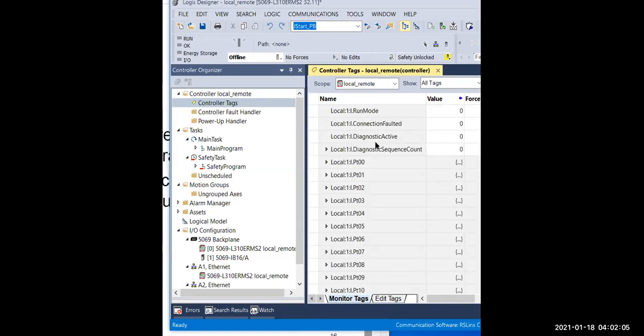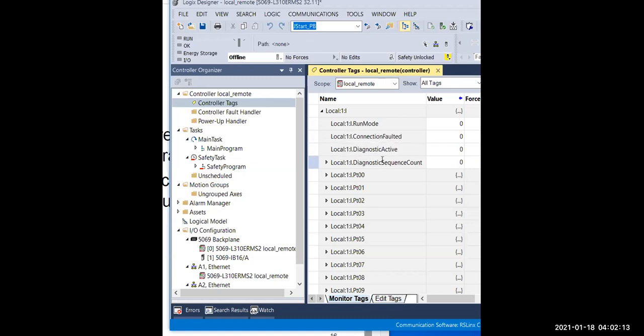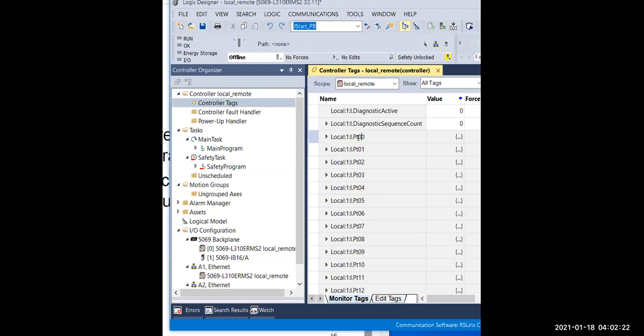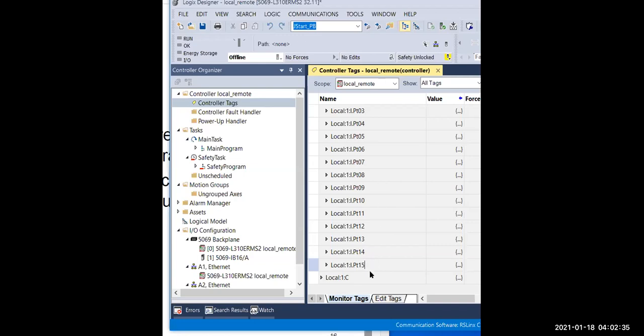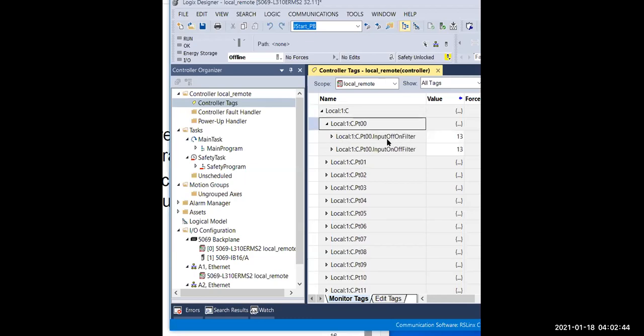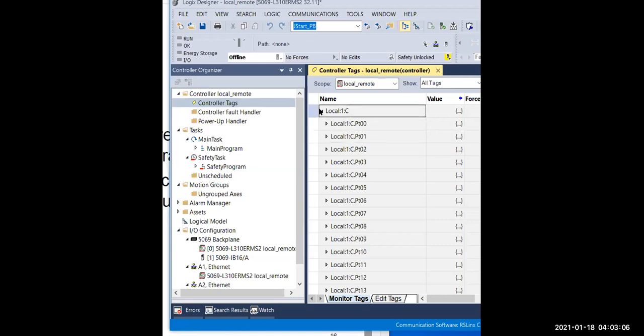Let's look inside the input tag. You can see what I mean by smart module — you can get actual information on this. The input data goes from point 0 to point 15, altogether 16 channels, each representing an individual connection point to the digital input. Now looking at the C (configuration) tag, you can see there's a filter setting. For example, if your signal has a bounce — flashing very quickly — you may want to apply a time filter on that signal, and you can specify that here. This is just the extra specific feature; the actual input/output data will be reflected in the I tag.